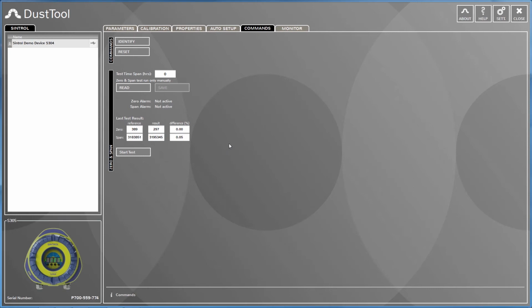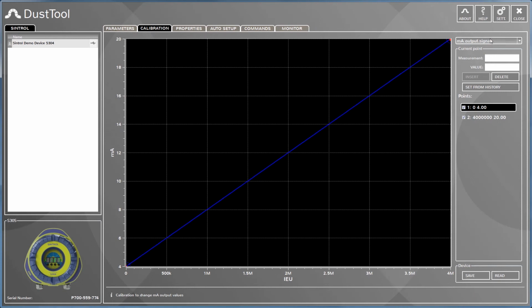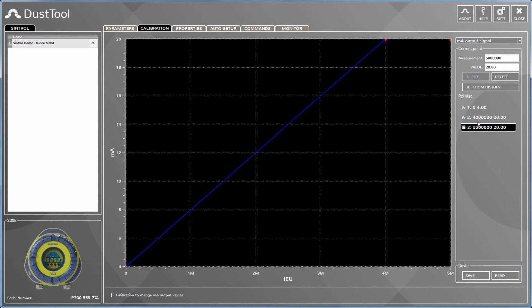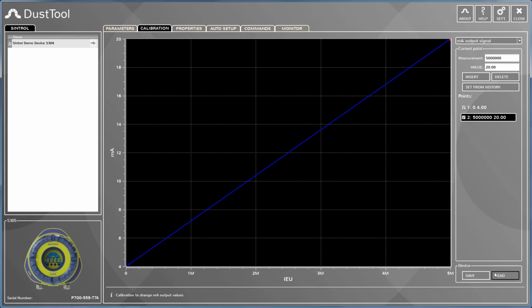There is one more thing to be said about the zero and span check, and this is the reference value against it is measuring. Basically, the reference value for the zero and span check will always be established when you are changing the milliamp output scaling. Meaning, let's say at the moment we say 4 million is 20 milliamp. Let's say we change that to be 5 million. Take that one away. Put this active. We save and we read.